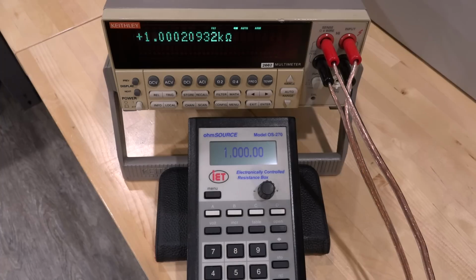Here's 1,000 ohm. Look at that, that's pretty close. It's very close to 1,000 ohm already. I still want to calibrate it. Let's try 10,000 ohm. 10, 1, 2, 3, enter. And let's see if it does 10,000. There it is, 10,000. I'm saying that's pretty good, considering that I haven't handled it and I don't know how old it is. When was the last time something like this was calibrated? We can try 50 ohms. Let's see, does the low value work or not? There it is, 50.085. So yeah, let's try putting it through a calibration routine.